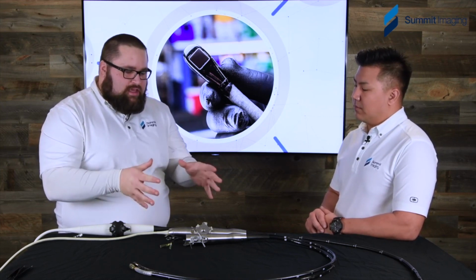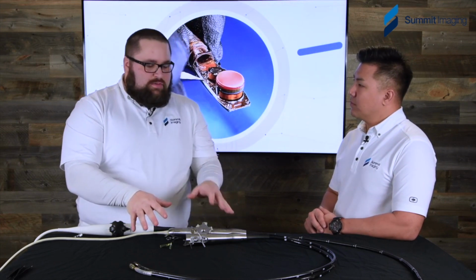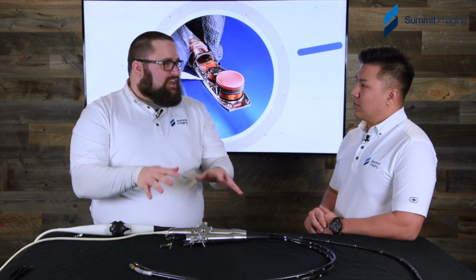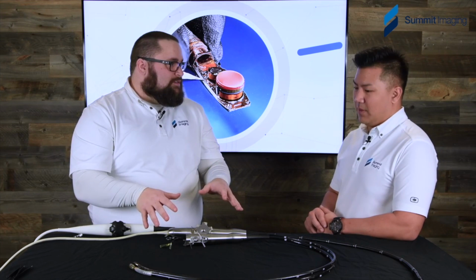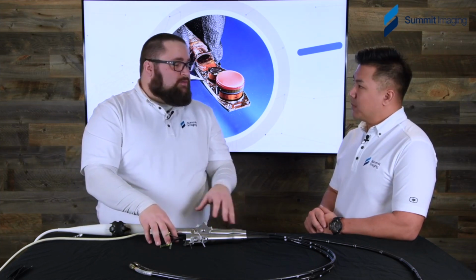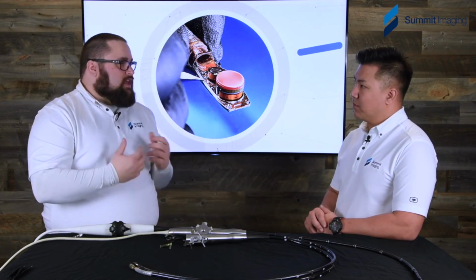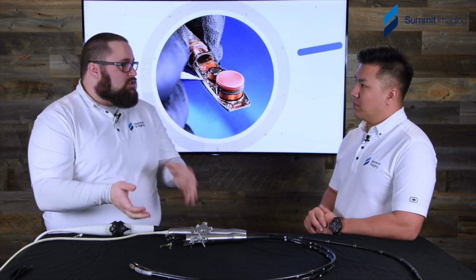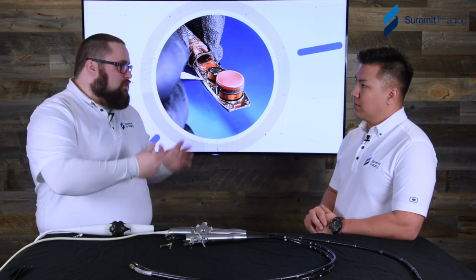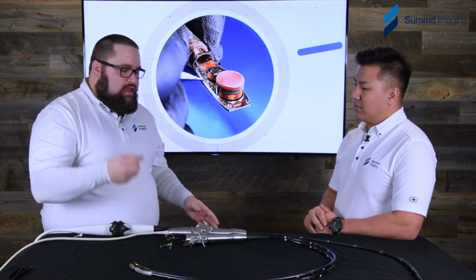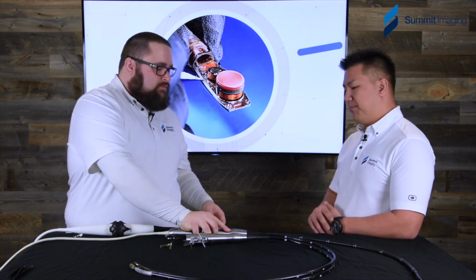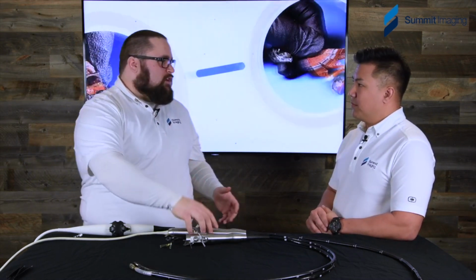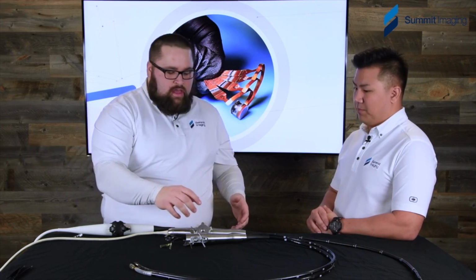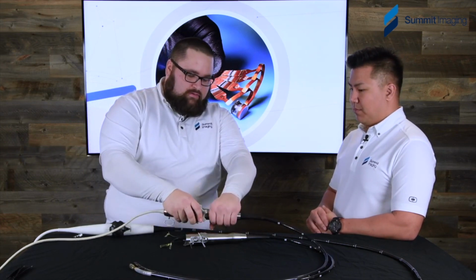But a lot of the issues happen in the handle, just because that's where, when you're sterilizing these, it's the best place to hold on to. And I've seen so many times they go downstairs, and the techs are working hard. They have more than just these transducers to get through. They have everything else that just came from the OR, and they grab this with their wet glove. All right, and it's water. It's just from the sink that's running. And it just gets into the handle, right?